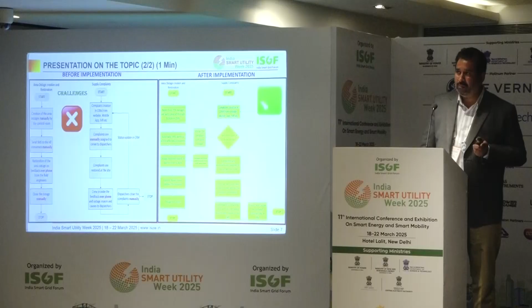After implementation, we tried to eliminate manual efforts wherever they existed. We now get power outages from the SCADA system in real time. Whenever a power outage happens, it's recorded in the SCADA system and reflected in the OMS system. An event gets created in the OMS system at the same time, and with the indexing already received from the GIS system, all customers get informed about the outage.